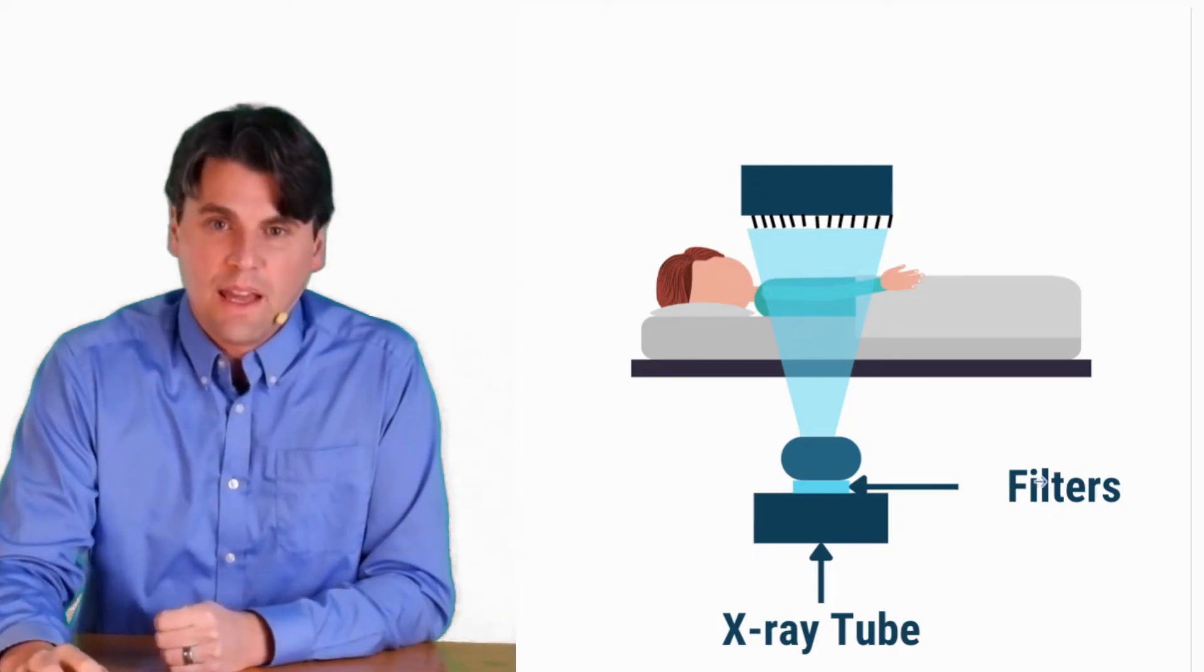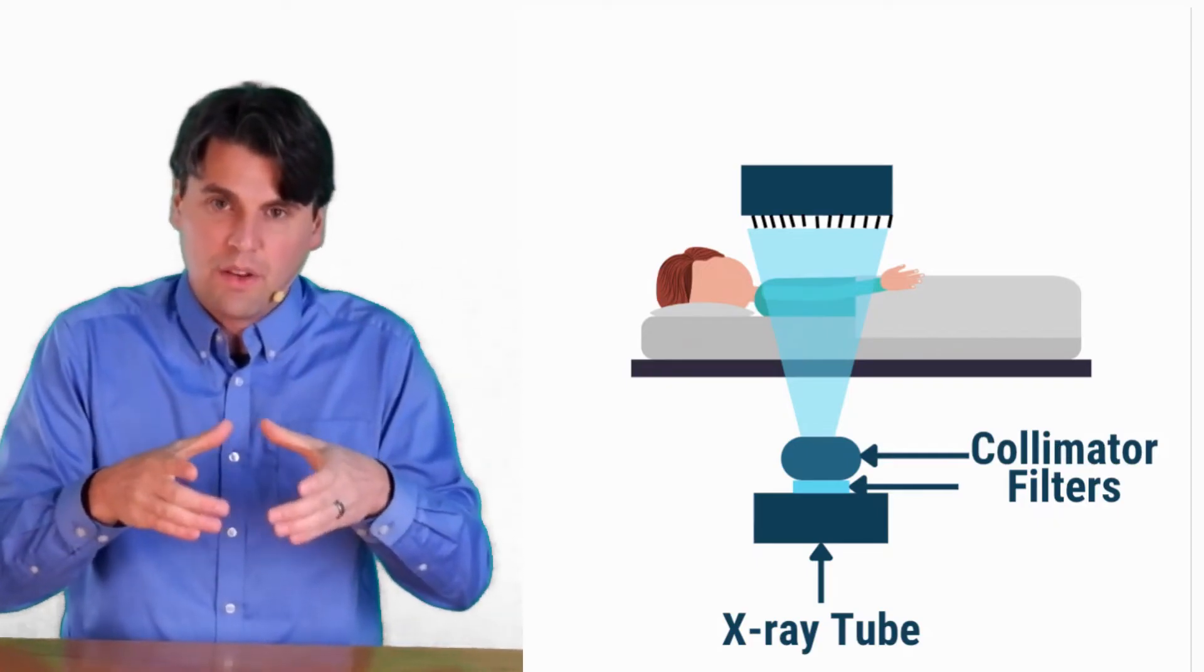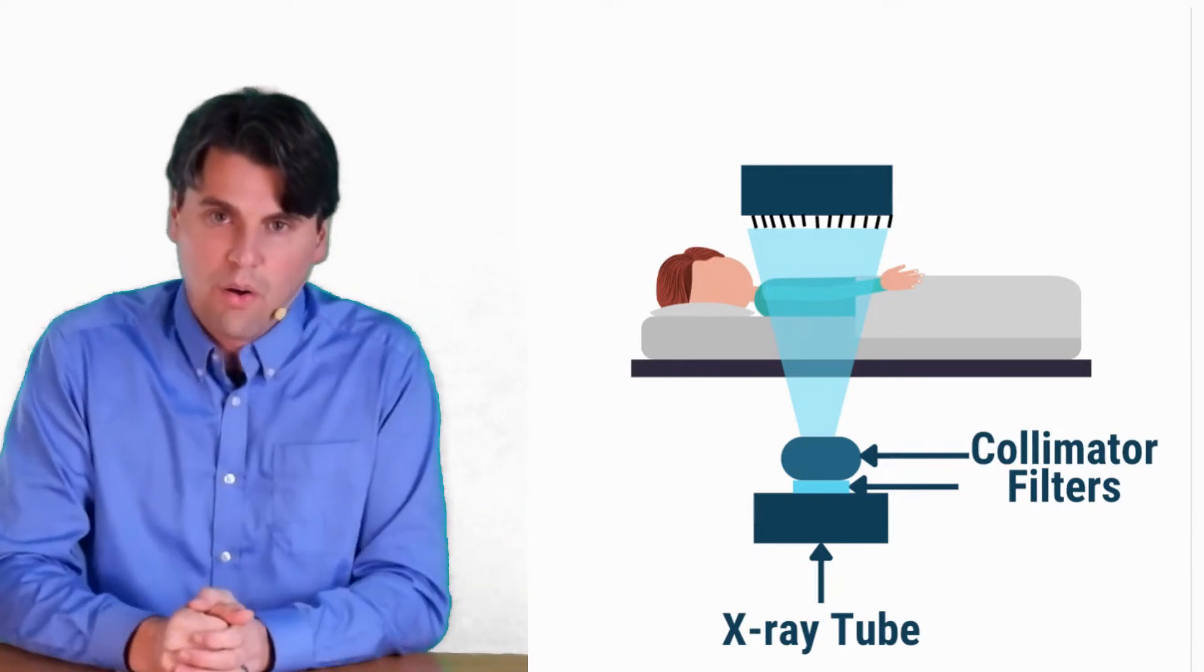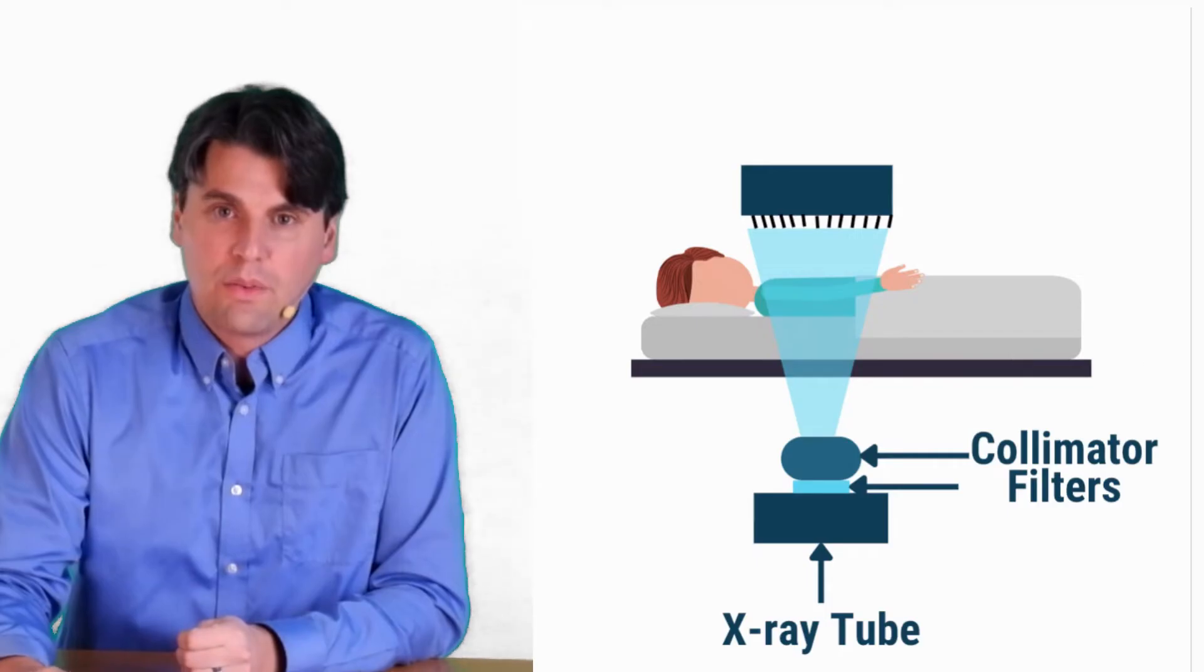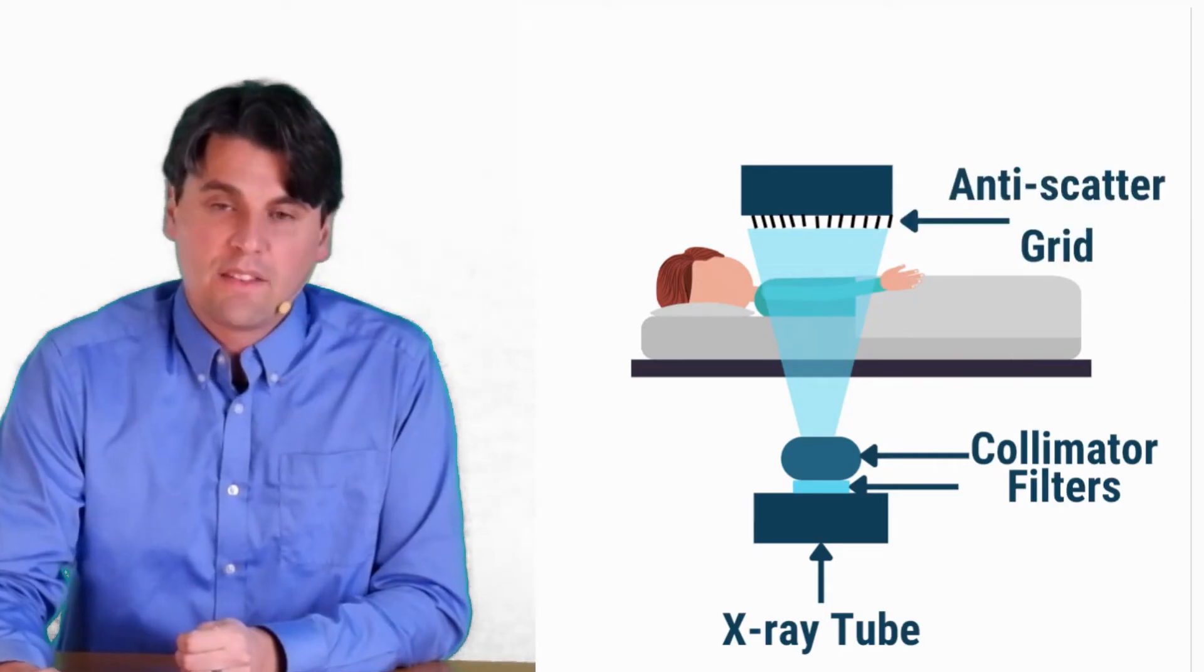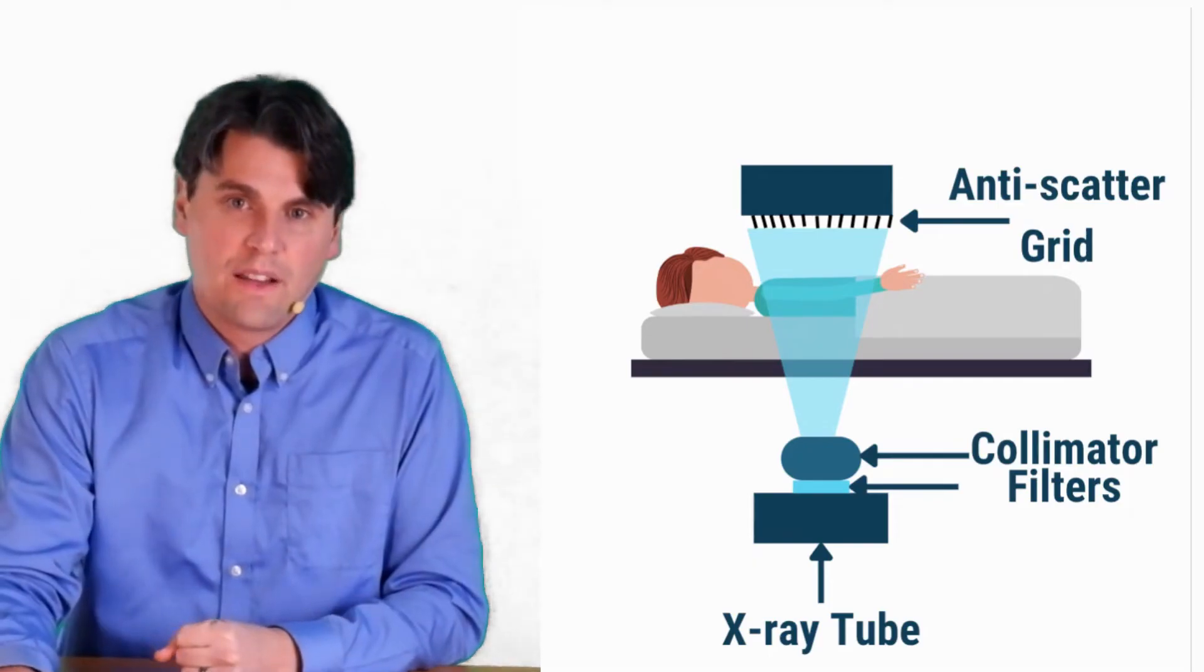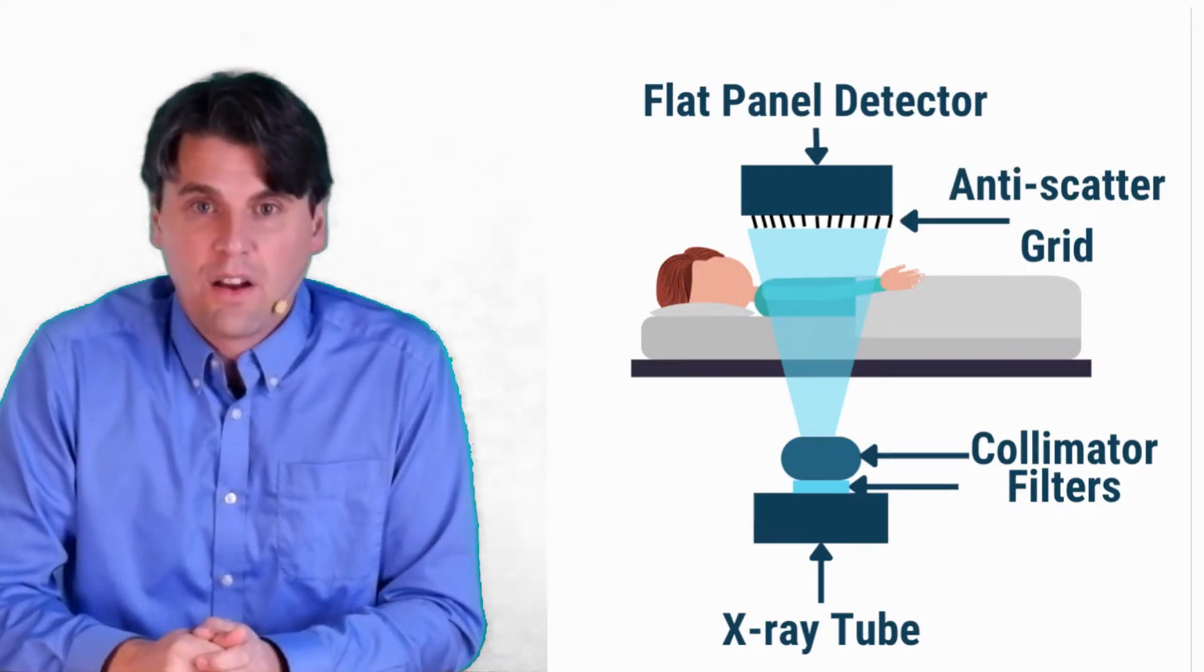And then there's going to be a collimator, which is going to actually block down and make sure that you're not irradiating more than the region that you'd like to show on the image receptor. The x-rays will then pass through the body, they'll then pass through an anti-scatter grid. If you have an anti-scatter grid on your system to try and reduce the influence of scatter.